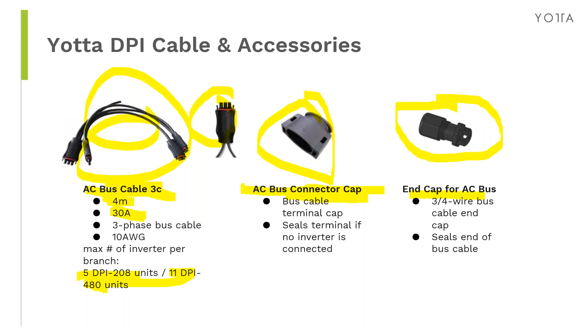If there's a chance where you need to skip a drop, this right here is the connector cap, or a dust cap. It keeps it dust proof and waterproof. At the end of the line, one side is going to be the home run towards the AC breaker, and the other side is going to be a cut end. This right here is the AC end cap for that. Watertight, dust tight. One question we do get asked is, okay, it's a 4-port microinverter, but let's say I only need to use 3. That's no problem at all. All we ask is you put on these rubber dust caps, watertight and dust tight MC4 caps. It keeps everything dry and protected.